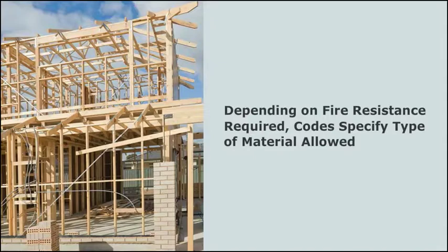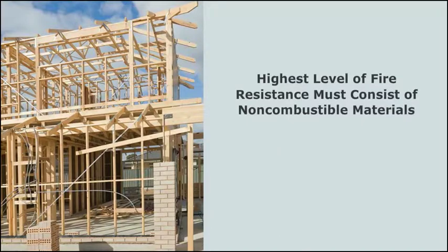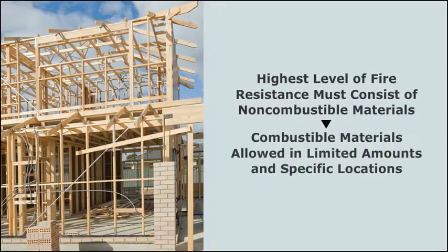For example, Type 1 construction, which requires the highest level of fire resistance, must consist almost completely of non-combustible materials. Combustible materials are only allowed in limited amounts and specific locations.